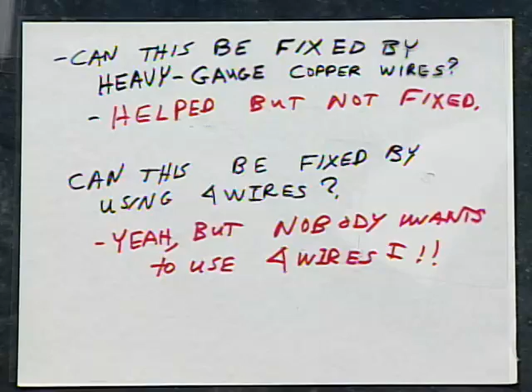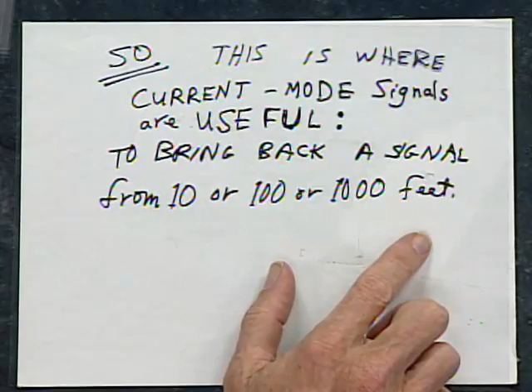This is a place where current mode signals are useful to bring back a precision signal from 10 feet, 100 feet, 1,000 feet, 3,000 feet. Why? Because the wire's series losses do not degrade the signal. 1 ohm, 2 ohms, 3 ohms, we don't care - the current through the ohms of the series path does not affect the accuracy.